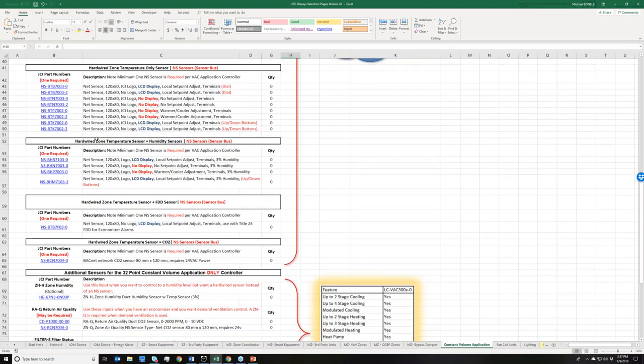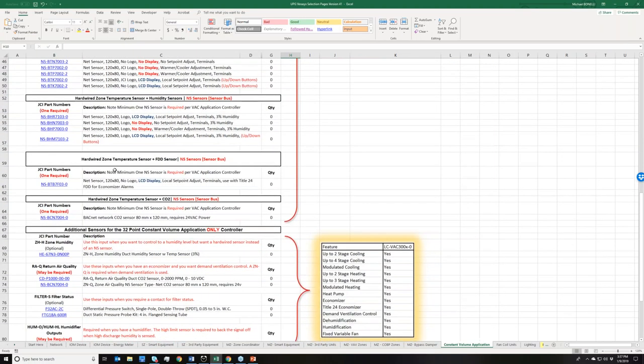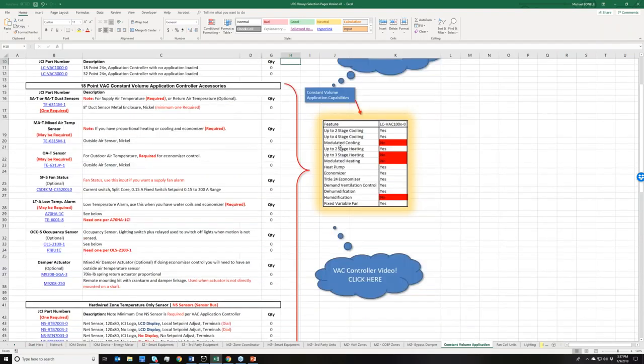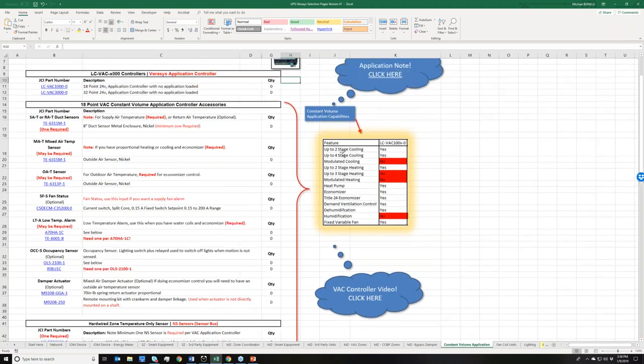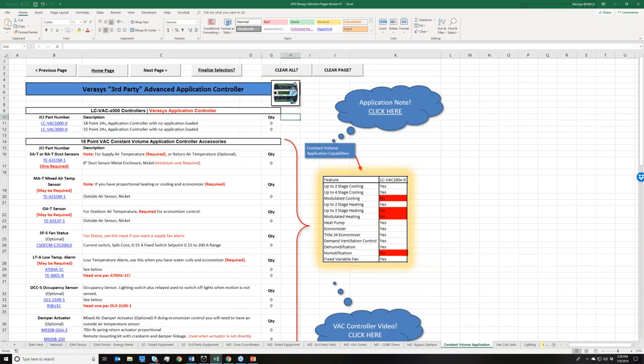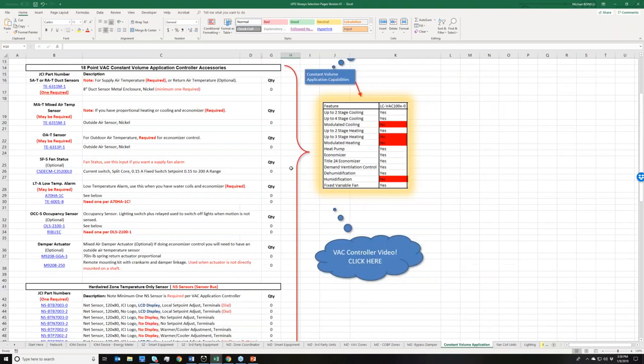The constant volume application would be used when you exceed the capabilities of the TEC thermostat, or you don't want a digital display inside the space. The 18-point controller can do everything the TEC thermostat for single zone systems can do, and it can actually do a lot more. The only thing it doesn't have is a display. This is mounted on the equipment, not inside the space where you'd have the touch screen.